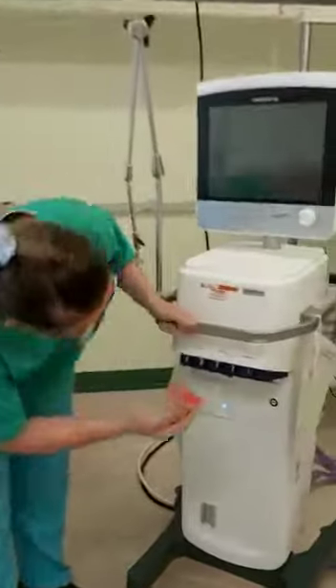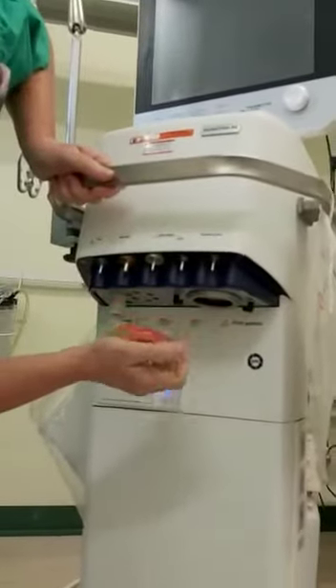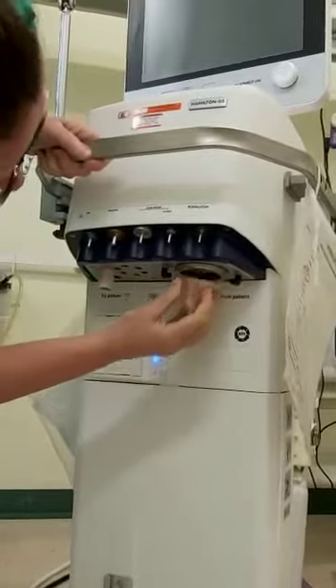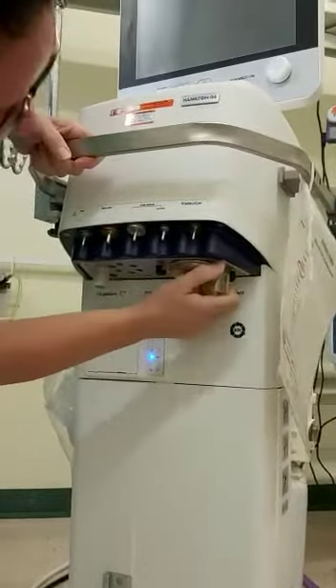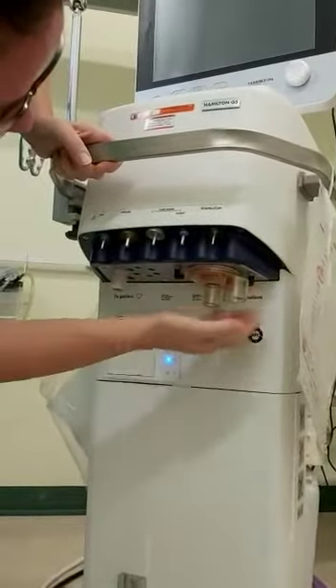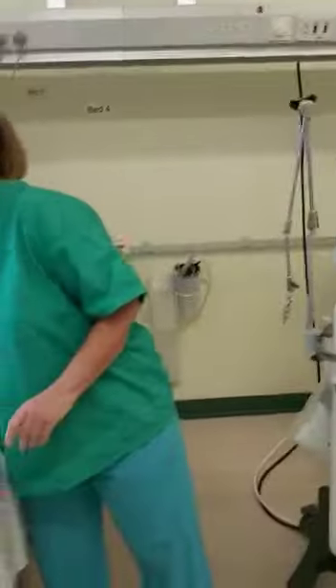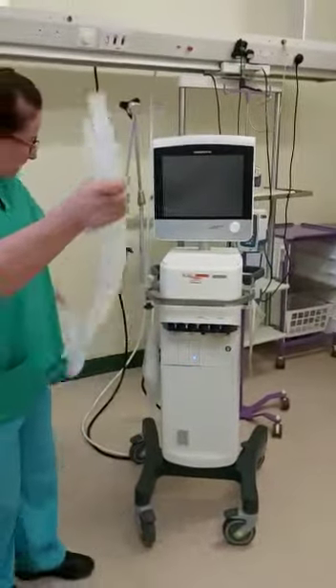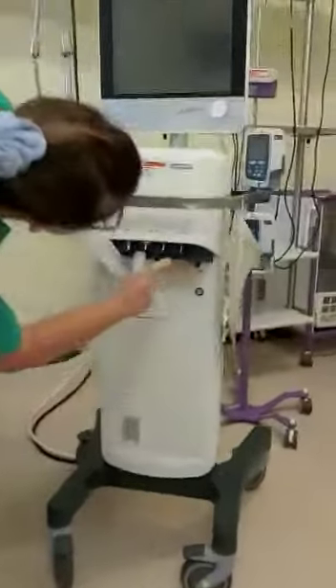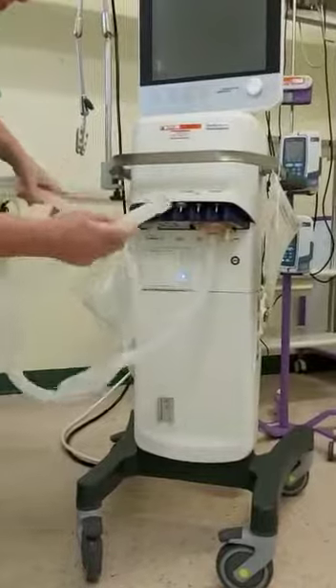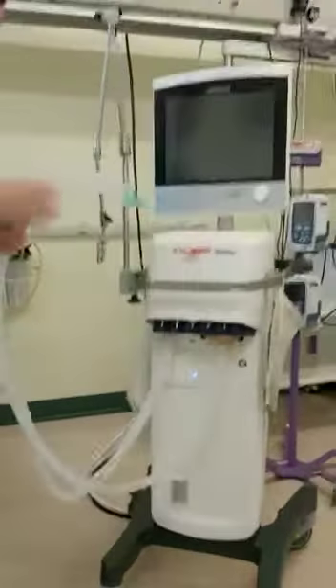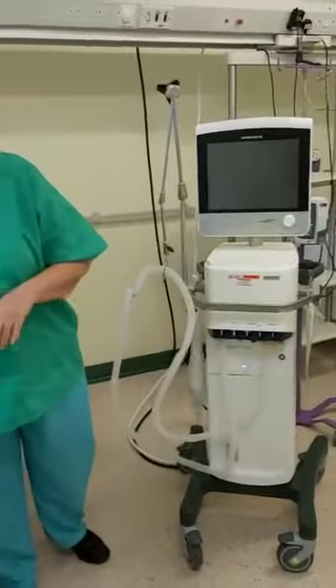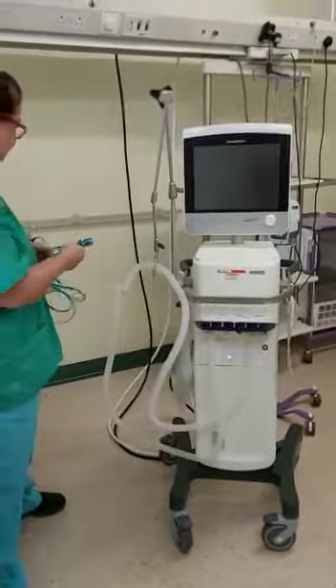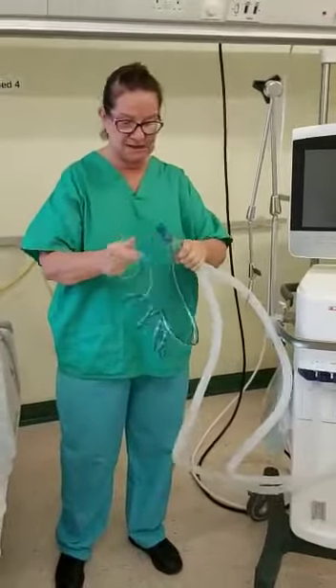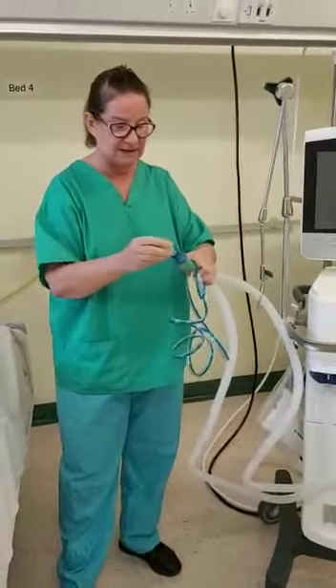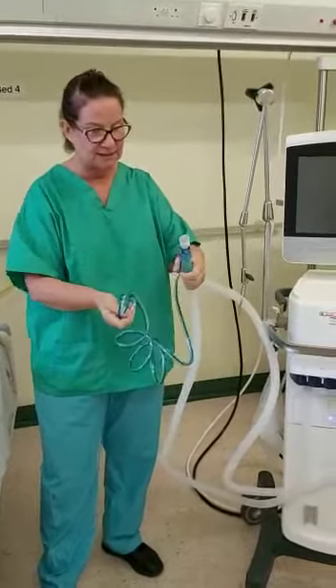So your expiratory valve is going to be put on first. This goes underneath the ventilator, and you've got a lip on either side which we're going to insert that into. So you just push it in and twist so that it's secured well between those two little clips at the side. You then want to take your ventilator tubing, and we're going to attach that to your inspiratory and expiratory limbs. So one onto here, your expiratory, and the other end will go onto your inspiratory limb, and then that can just clip into your supportive arm. Your flow sensor can then be attached, so that just clips onto the end of the ventilator tubing, and it's quite useful at this point to use your little adapter and just put that in place ready for when we're calibrating, which we'll do in a minute.